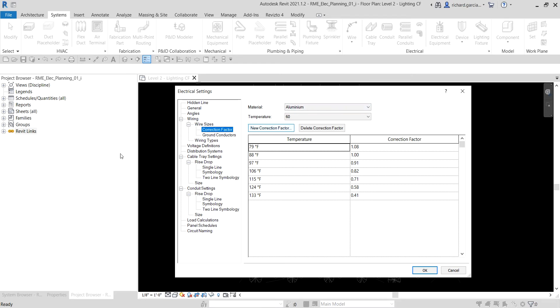The first thing we're going to do is work with the correction factor. The correction factor is used when calculating wire sizes in the project. Ambient temperature affects the current-carrying capability of wire, and this effect is specified as a value for the wire material at specific ambient temperatures.